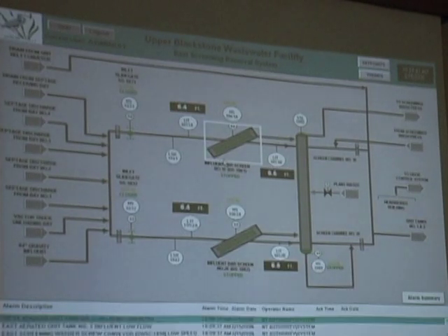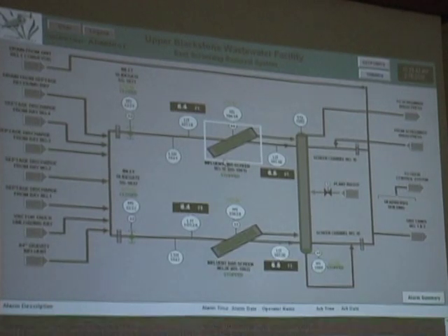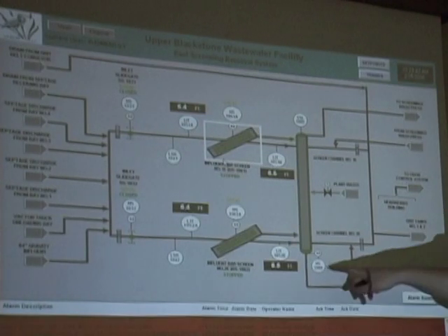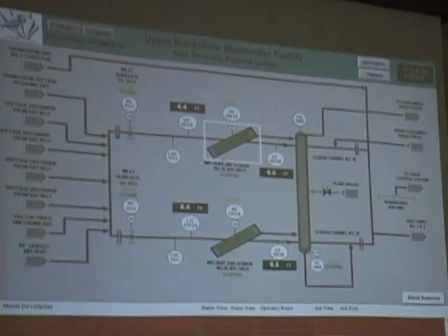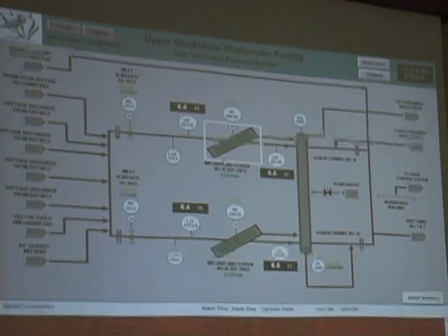So trying to keep the autos and manuals separate, we've now called the switch out in the field a local-off-remote switch, meaning you either have local control, off, or in remote, which would be us. That way when you're in remote auto, that means that you're controlling it automatically through the Scada. If you're in remote manual, that means that you're controlling it manually through the Scada. Okay, that's usually a little confusing, but every piece of equipment shows a status if it has a hand-off-auto in the field. It'll either show you that it's in local or it'll show you that it's in remote. And if it is in local, you can look at it, but you can't actually do anything to it.